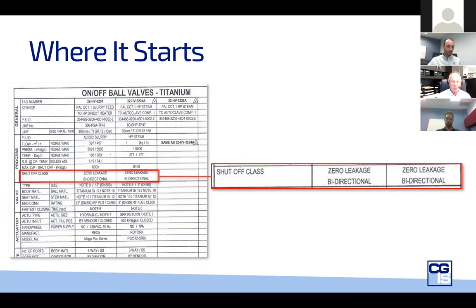We tested the valve properly to a requirement of zero leakage, but in actual fact it failed to last more than 17 weeks. The point is that we really need to focus on how do we get the required performance of a valve into the valve for its actual life in the application. Here's another example — a quite good data sheet providing critical information: bidirectional bubble-tight as per API 598, and fields for scaling potential, corrosion potential, erosion potential, and abrasive potential. This really assists in understanding the pitfalls the valve may experience when it's actually in line.